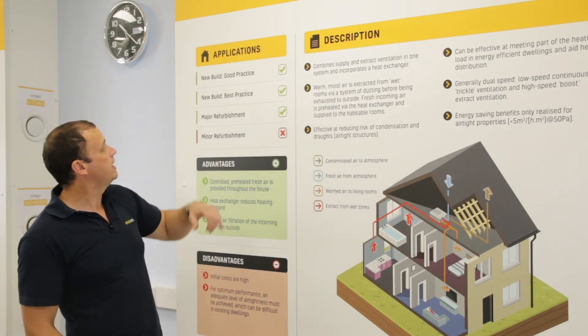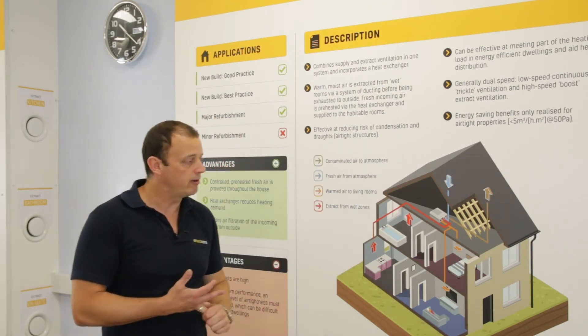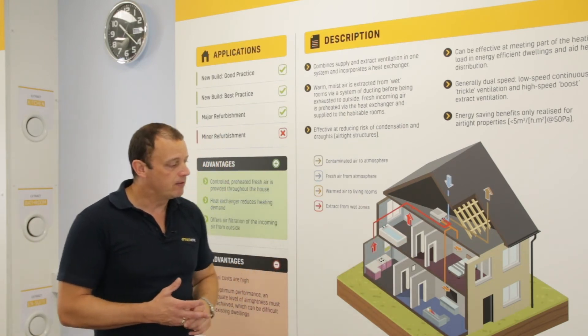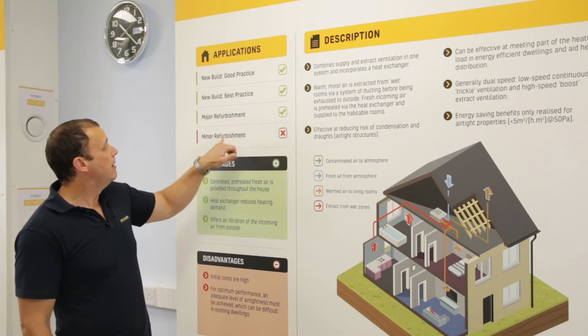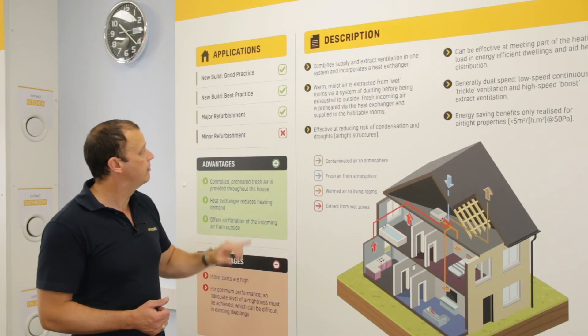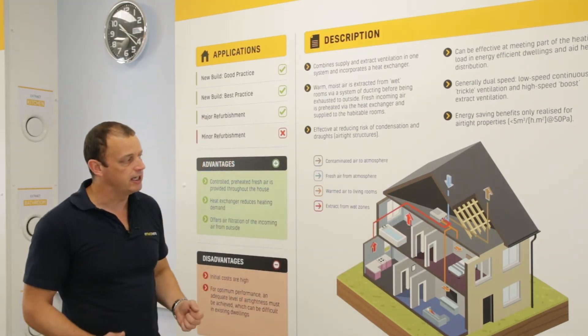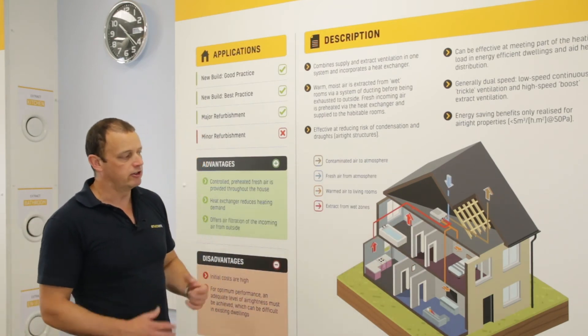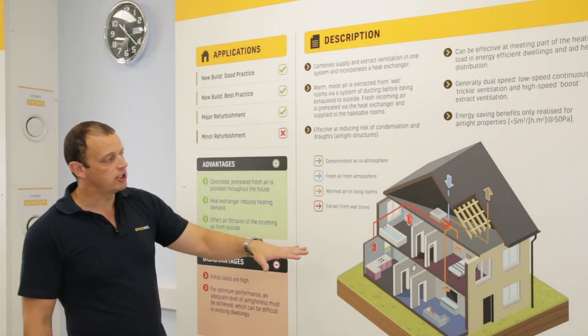That is heat recovery in summary. It's recognised as best practice for new builds and airtight dwellings because you're getting that heat recovery - it's very good for your heating system and keeps energy consumption down. For a major refurbishment it's good because you can get ducting everywhere, but for a minor refurbishment it's not recognised as best practice because you've got to run ducting - you'd have to pull ceilings down or box ducting in along the sides of rooms. A lot of work involved, but a very good system.